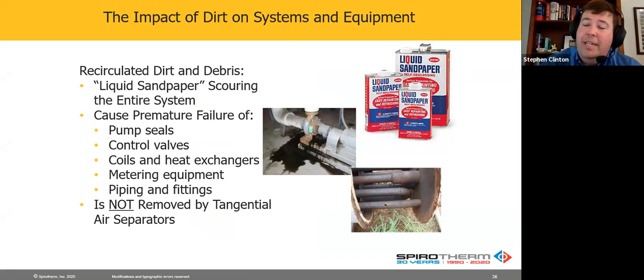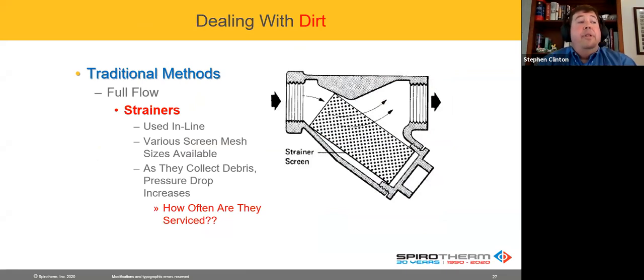So how have we typically looked at that as an industry? Well, there are different ways. Oftentimes these are catch and hold methods. They're filtration, or they're strainers or filters. The first type is just the strainer. Strainers are good, especially for catching big things. But when you get into small things, they start to load up, and that can be good. It's like an air filter on your house. The more it loads, the better it works. But what happens to the pressure drop? It goes up significantly. That affects your pumping system. The other thing is, oftentimes, how many of those strainer baskets actually are ever serviced?